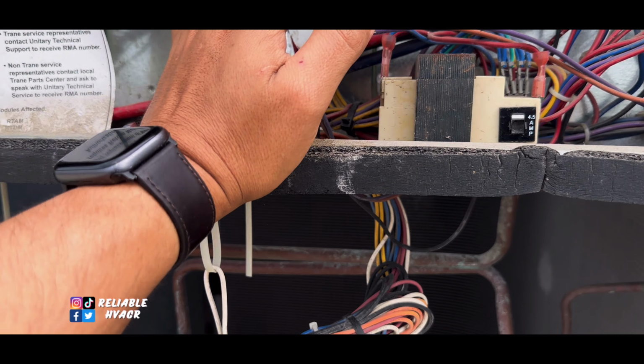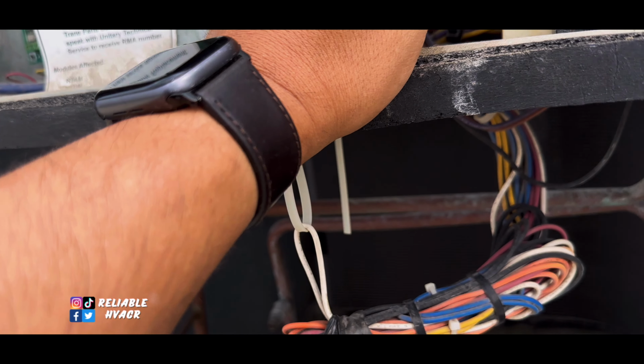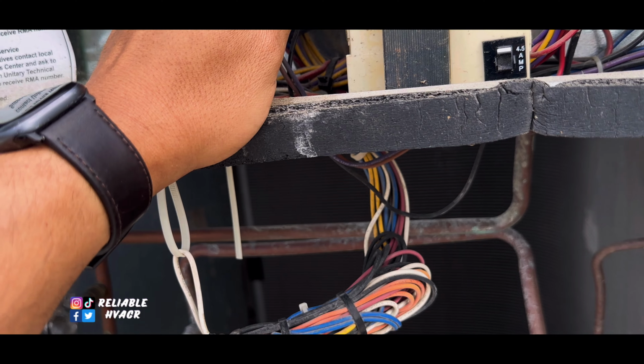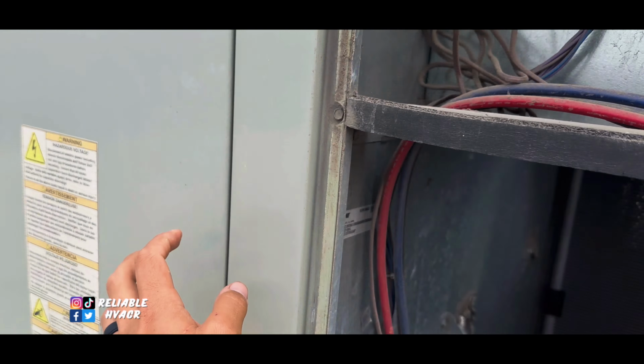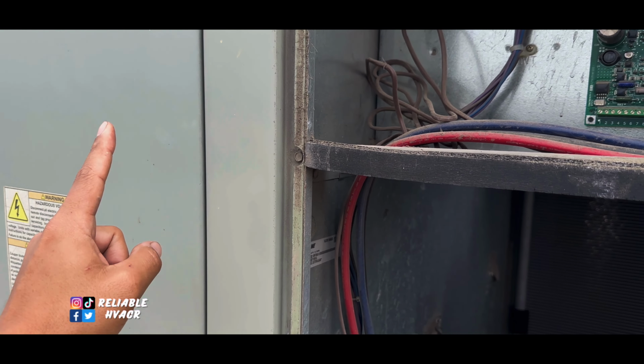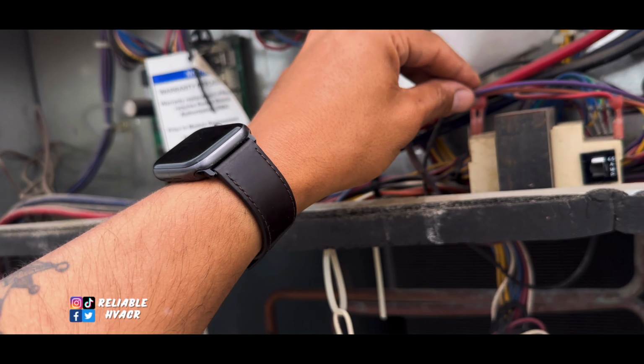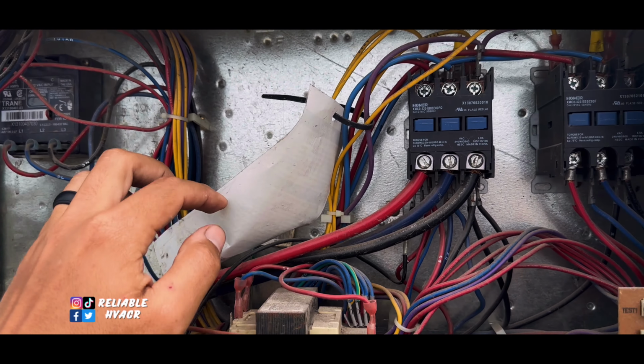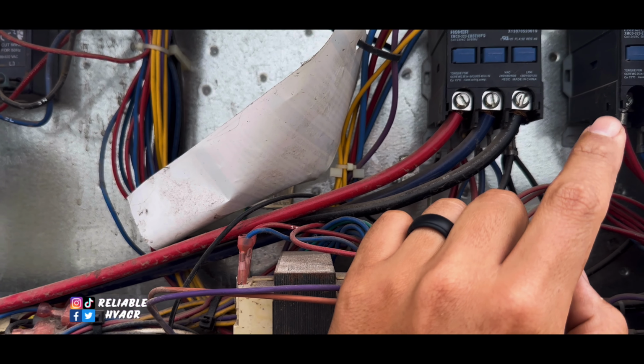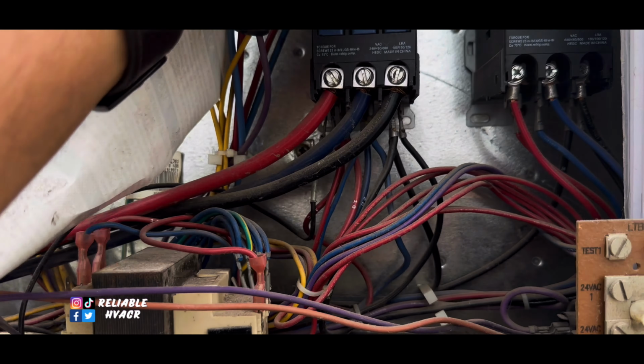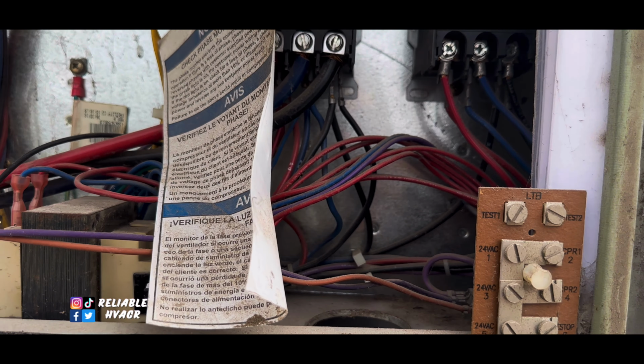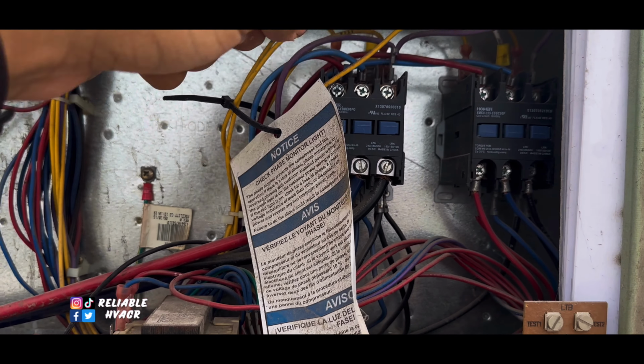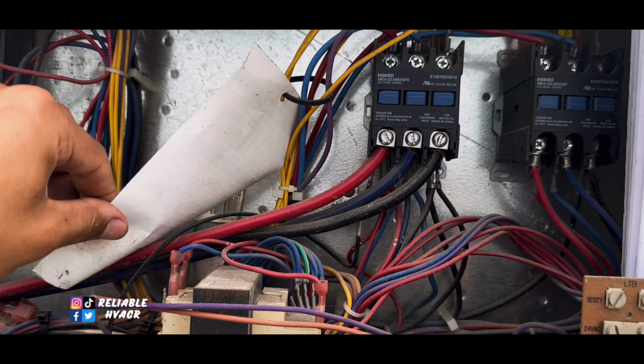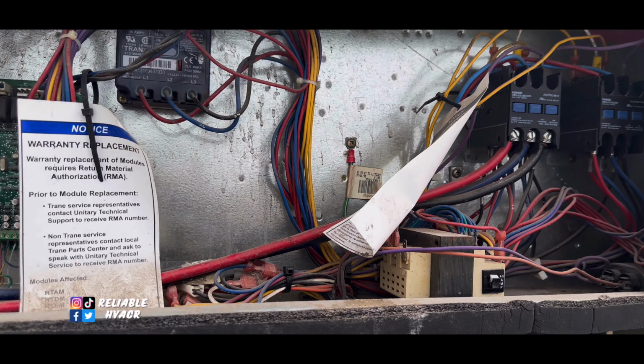Yeah, I'm more than sure this has one of those DC motors, and we had to replace that immediately after it was installed. Another company installed it. We're also going to check the contactors. That's a super simple one: if you don't have resistance on your coil, and those go bad, then you get shorts too. So let's check it out.